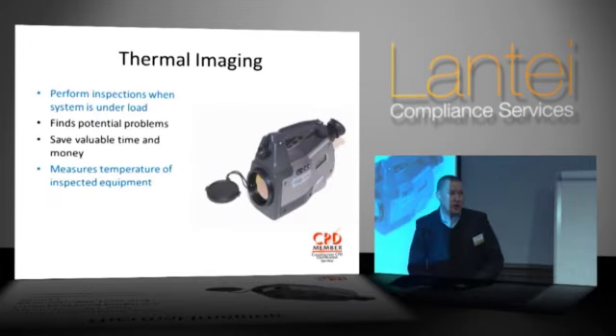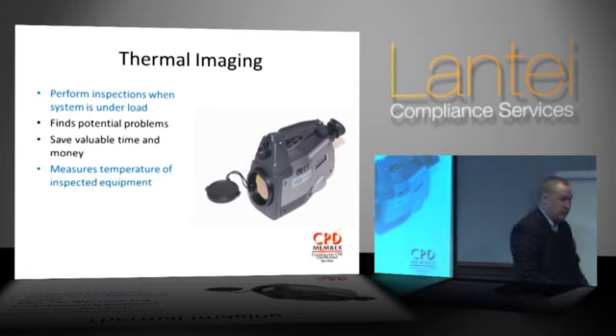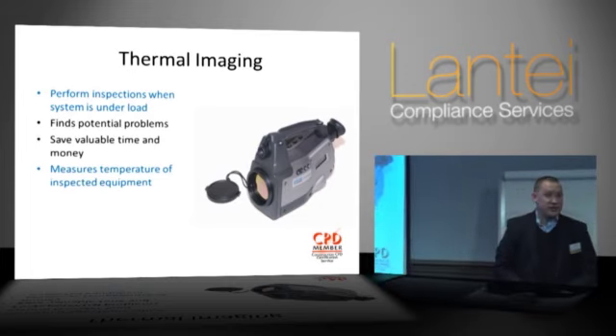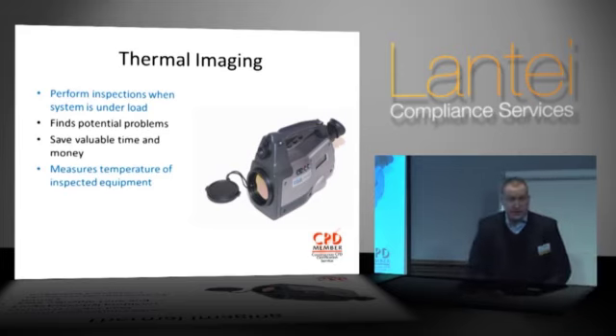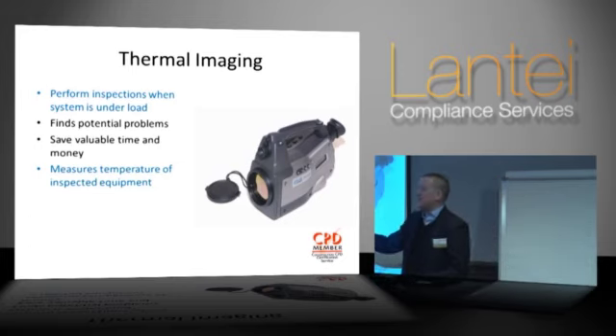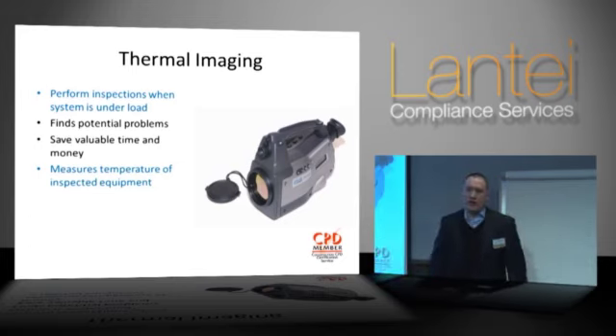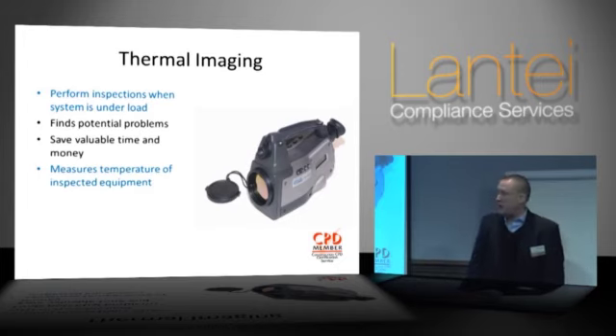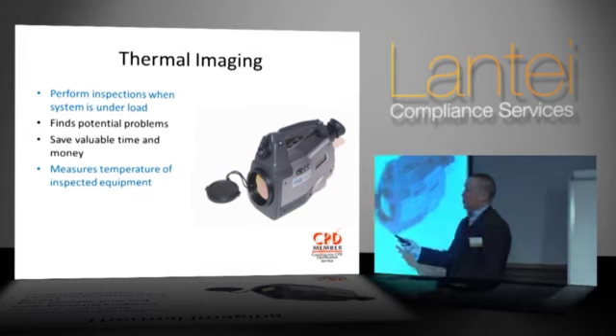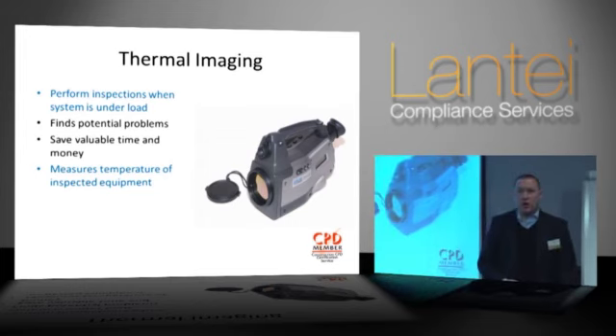Right, secondly, you can look at getting thermal imaging carried out. Again, the beauty with thermal imaging is it allows you to carry out the inspections with the system operational, with the system under full load. As with the mains analysis, what it's helping you to do is identify problems before they become catastrophic, before they cause unexpected power loss. Net result, again, we're back to making informed engineering decisions, and that's going to save you valuable downtime, and therefore it's going to save money. In effect, what does it do? Well, it measures the temperature of the equipment that you're physically inspecting.